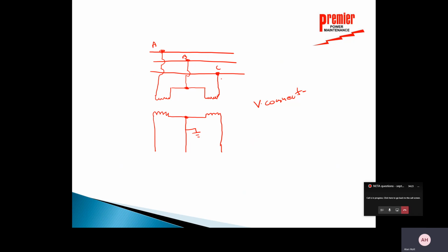So I've got A, B, and C phase voltage here. I've got A to B right here, and B to C right here. But A to C is still a voltage that is common, whatever's on this line. So I've got all three voltages present there. But I'm using this transformer in a special way. I'm only using 2 PTs, but I'm going to get everything out I want, because here I've got A, here I've got B, and here I've got C. I've still got all 3 voltages, and I've got a ground here on B phase because this is a completely separate system. There's no electrical connection from one to the other. They influence one another, but it's not electrically connected. So I can put a ground on this secondary side anywhere I want to, and I chose to put it right here on B phase.